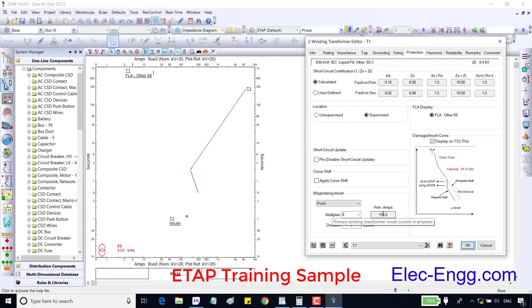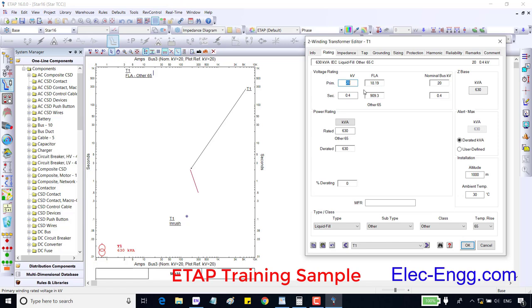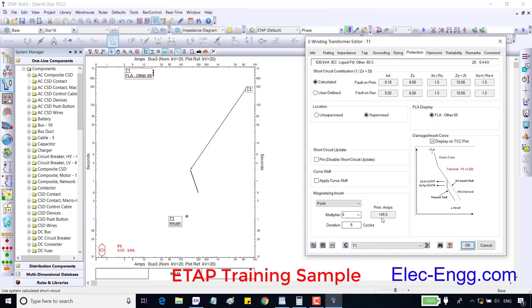Inrush current in the primary amp is showing here. This value is 8 times of the FLA in the primary. FLA in the primary side is 18.19, times 8 is 145 amp.